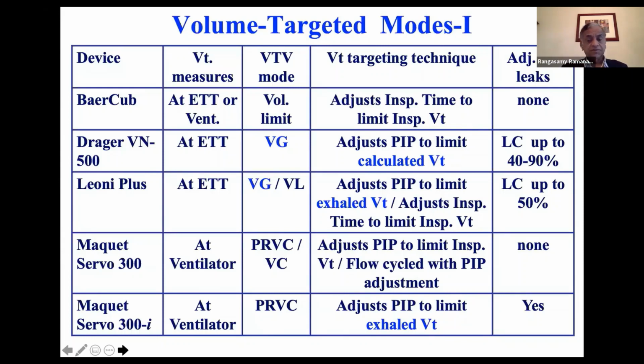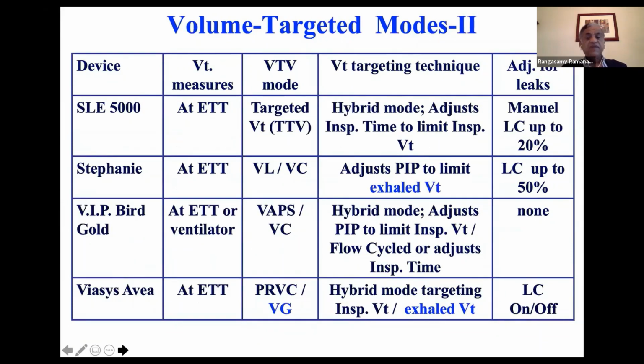Here is SLE 5000. It's a hybrid mode. They measure at the endotracheal tube and adjust the inspiratory time to limit the inspiratory volume. Stephanie, exhale tidal volume. VIP Bird, it's a hybrid mode. Viasys, at the endotracheal tube. So again, as I mentioned, each ventilator does it differently. So know how your ventilator does volume control mode or volume guarantee mode. That way, you really are helping the babies and delivering what you think.